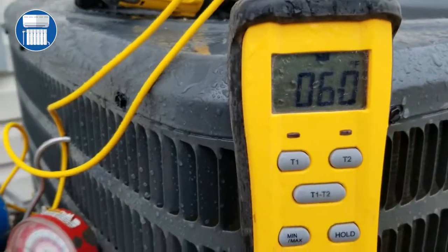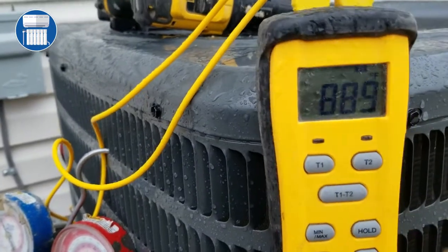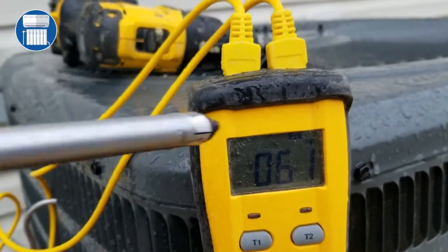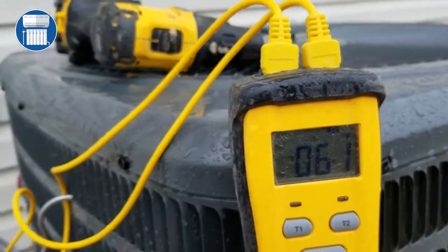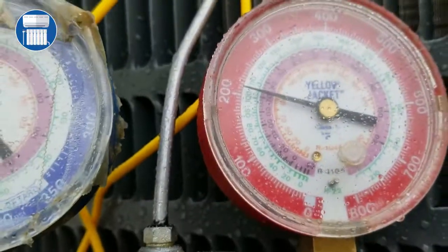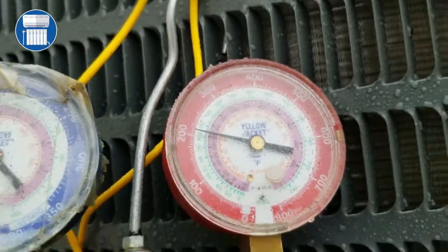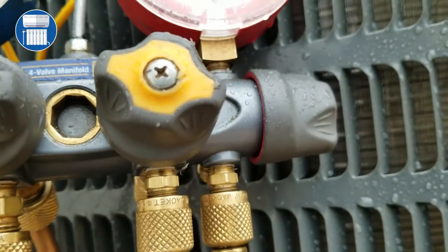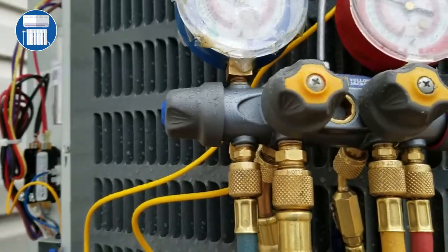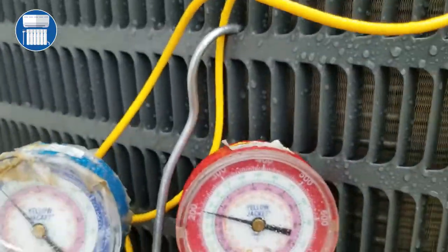I have the pipe temperature here — I have T1 and T2. T1 is my liquid line temperature, so you could take your line temperature from here. We're gonna look at the pressures and how to understand the manifold gauge. The red side is always our liquid line, so we connect the red line to the high side, which is the smaller port, and the blue line for vapor goes to the bigger port or the vapor port.